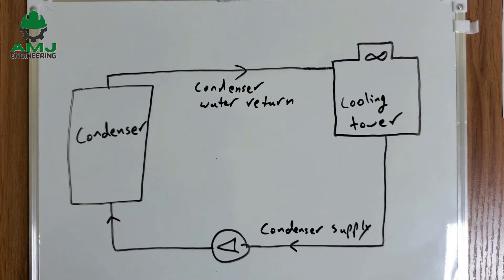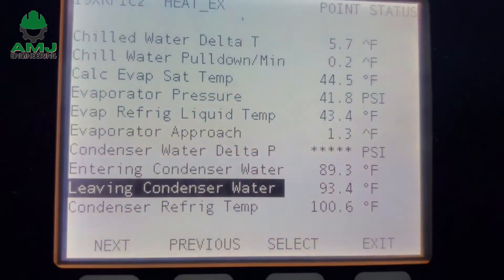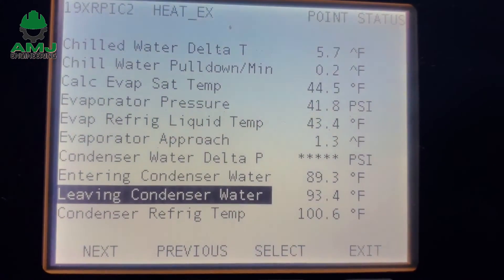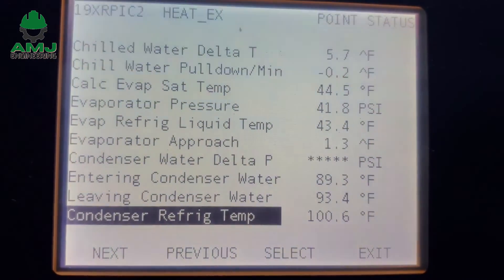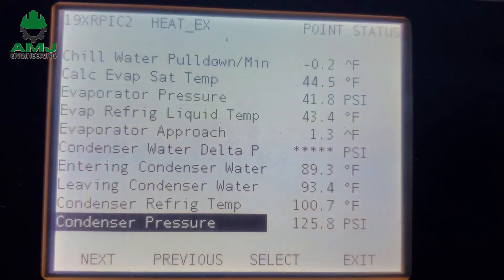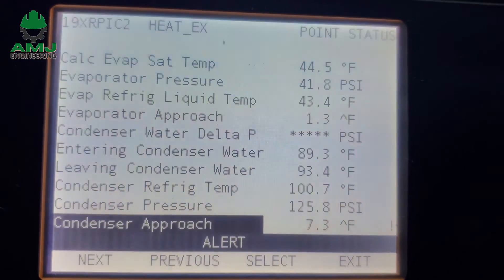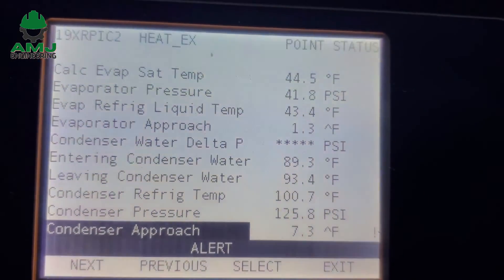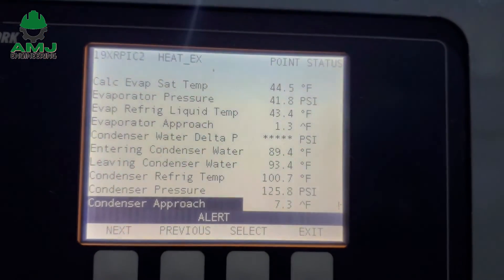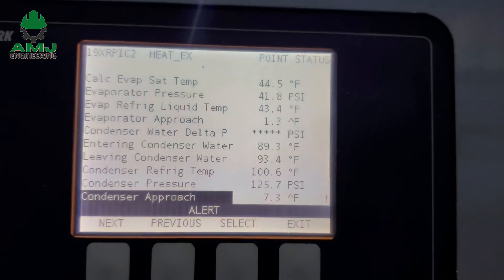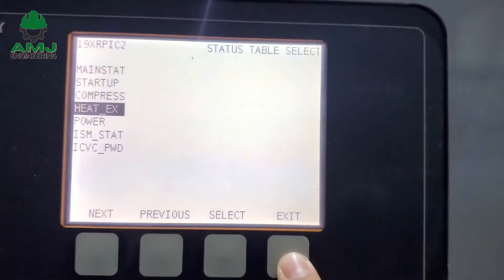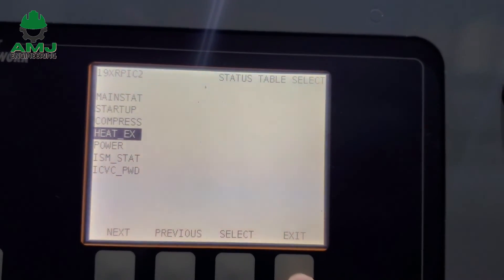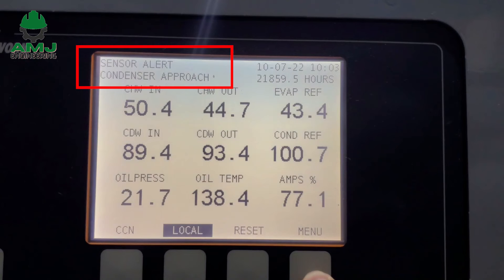The normal chiller condenser approach is below 7 degrees Fahrenheit for well-maintained chillers. In our case, the leaving condenser water temperature is 93.4°F and the condensing refrigerant temperature is 100.7°F, giving a condenser approach of 100.7 minus 93.4, which equals 7.3 degrees Fahrenheit. That is why we are getting an alert here due to high approach.